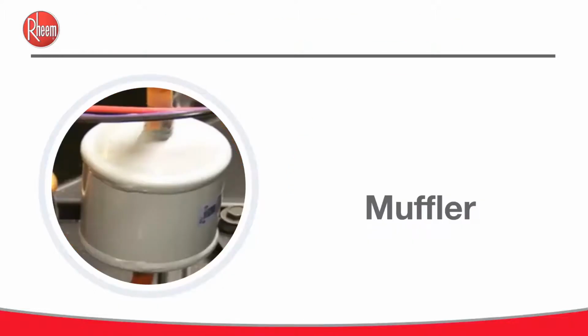Muffler. Again, mufflers, you don't see them on ACs. They are used to remove both low and high frequency pulsations, and they are located on the discharge line of the compressor on heat pumps. Thing to remember here is after time, you may not be able to read what's on there. Don't make the mistake of thinking that's a liquid line dryer. If you do, you're going to find out really quickly why it should have been a muffler and not a liquid line dryer.